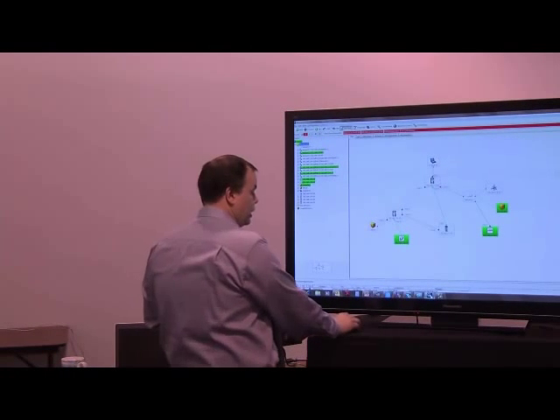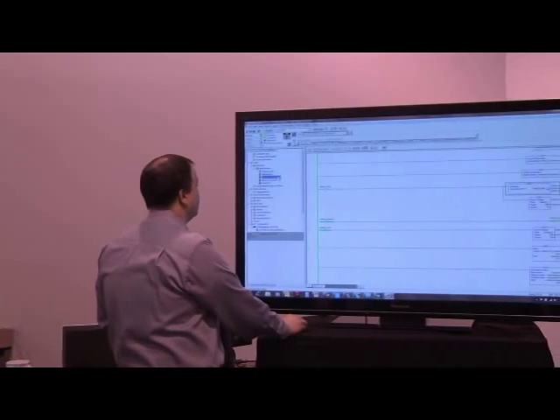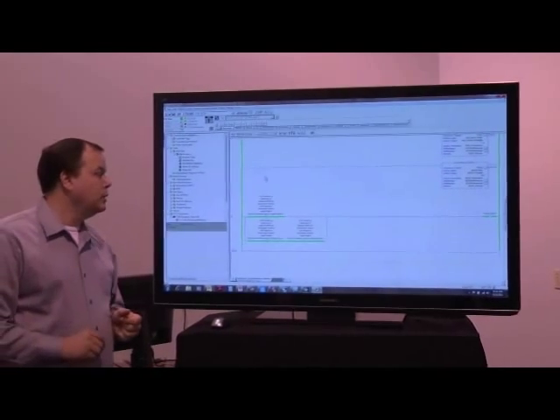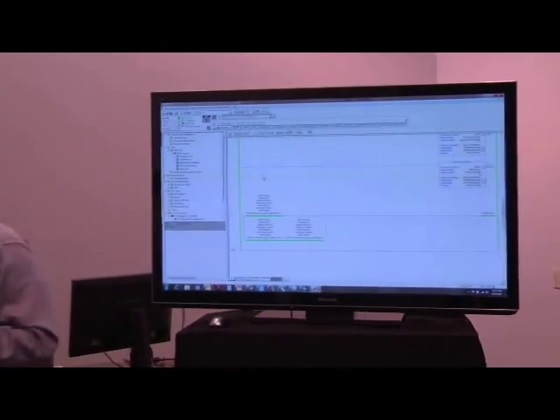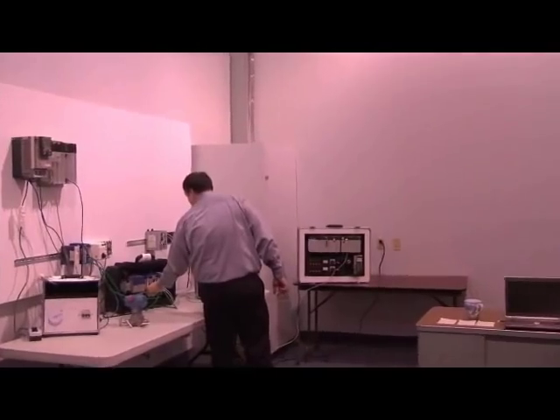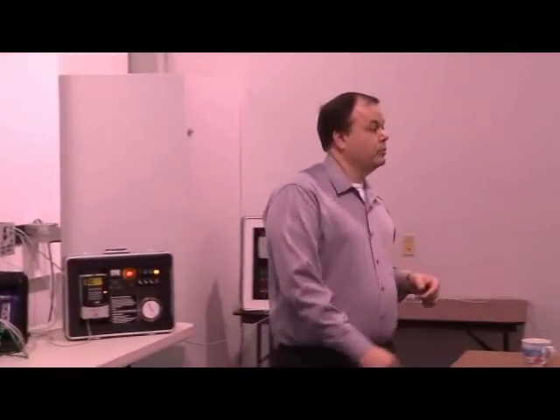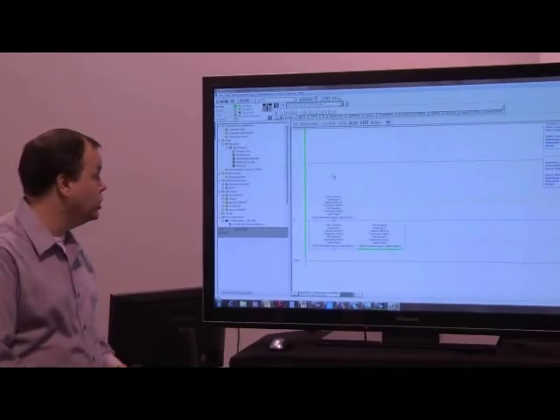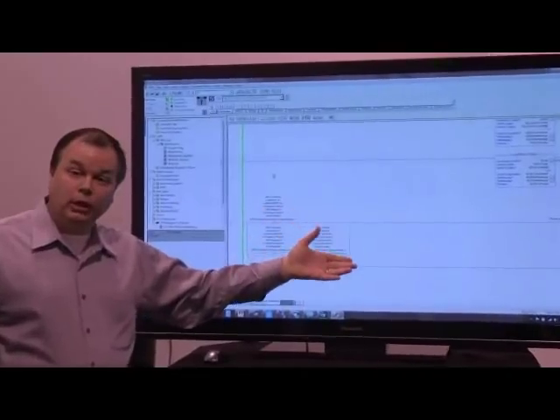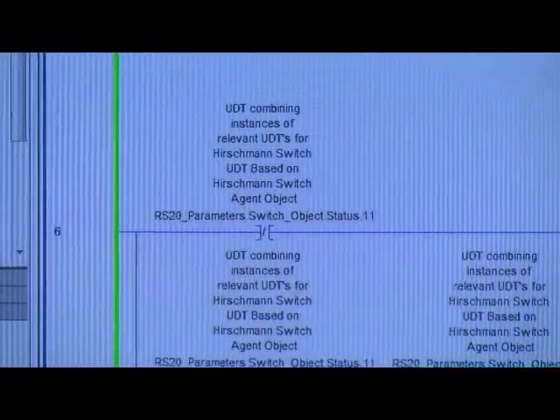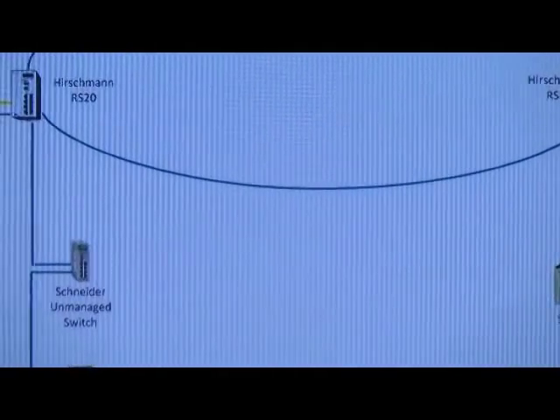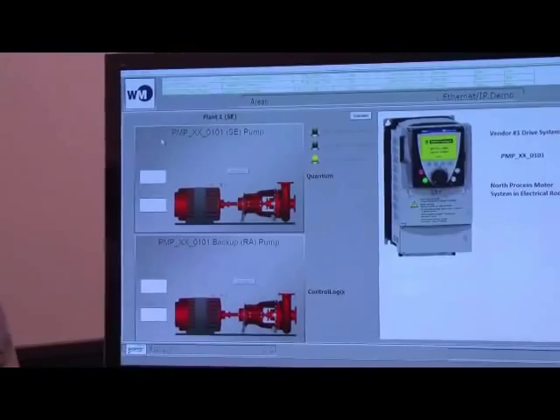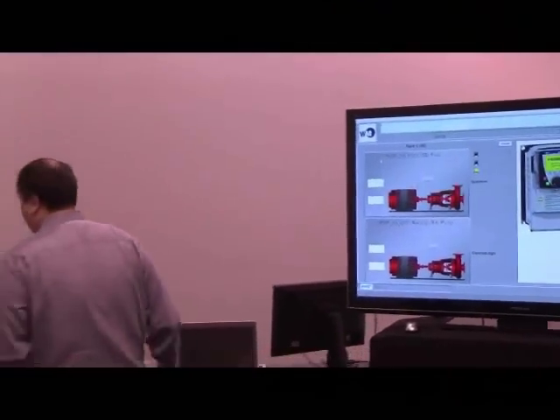Another tool specific to Hirschmann and Rockwell is that we can set up an explicit communication between the switch and the PLC that looks for any trouble statuses. The PLC has detected from its Ethernet IP communications to the switch that we have an alarm, and we can generate an alarm within the PLC to trigger some action or send it up to our SCADA application — for example, a flashing light or alarm on our system showing that we've lost the network or that there are problems on the network.